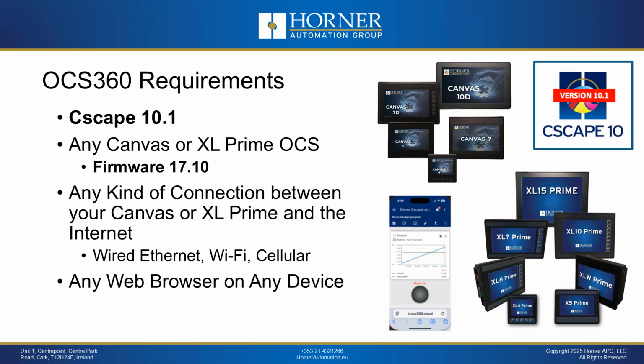Now let's talk about the requirements. Because this is new, you will need Cscape 10.1, and this is the version you are going to need. You are going to need either a Canvas or Prime controller, and that controller is going to need a firmware version of 17.10 or later.